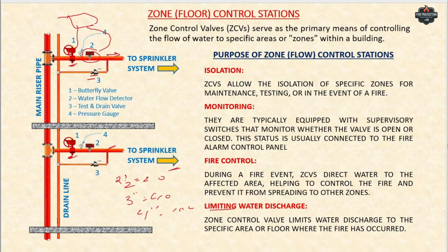And again here you can use either a gate valve or a butterfly valve, which is the supervised type. This is your main riser pipe. This one, main riser pipe. This is the drain pipe. Suppose you want to drain the system for some reason, open this valve and all the water will come down.